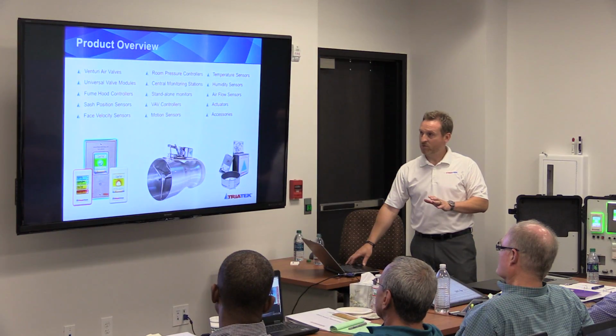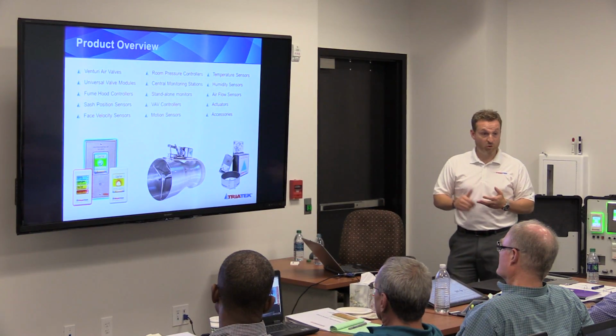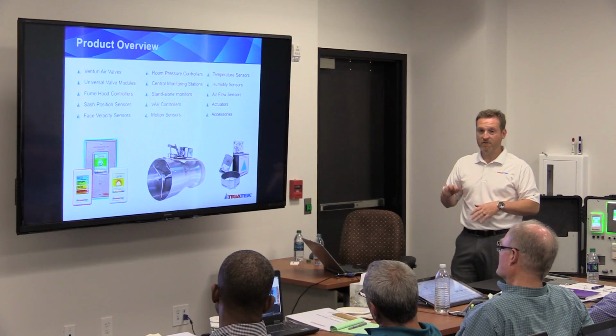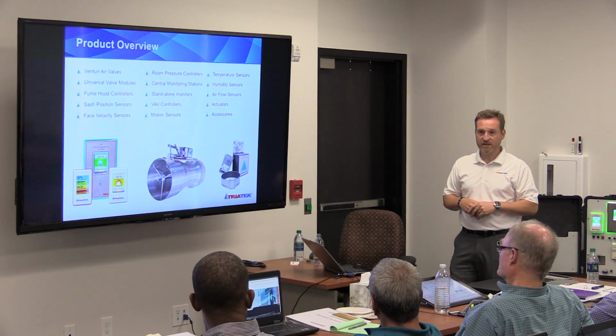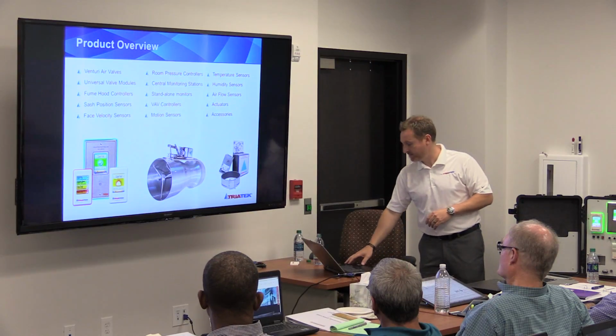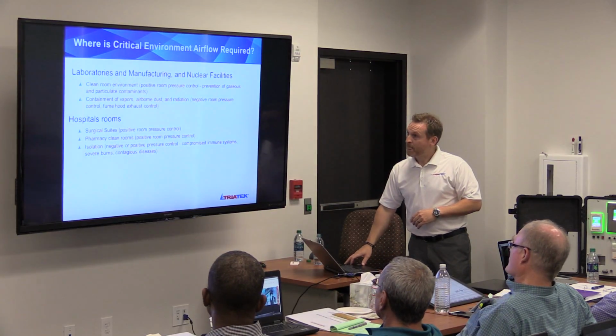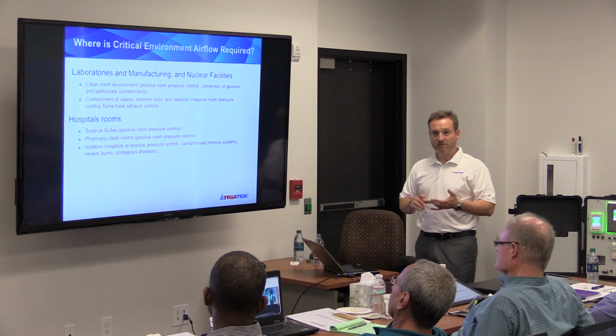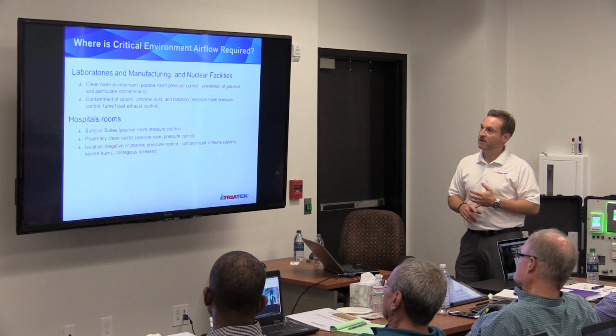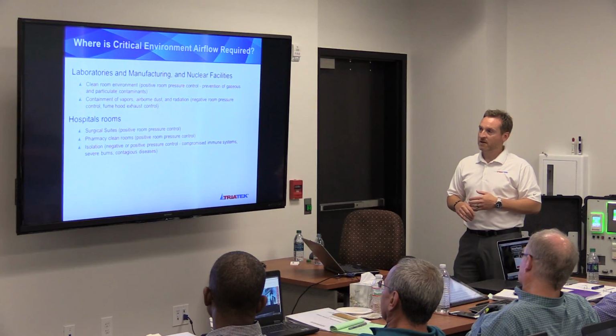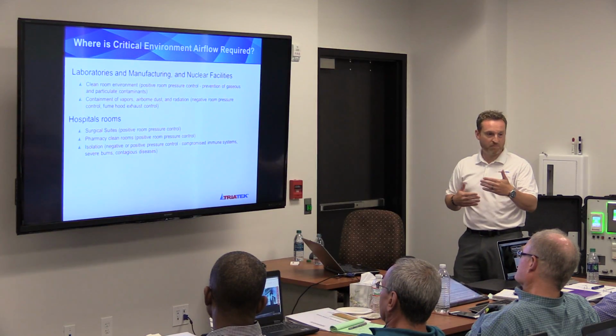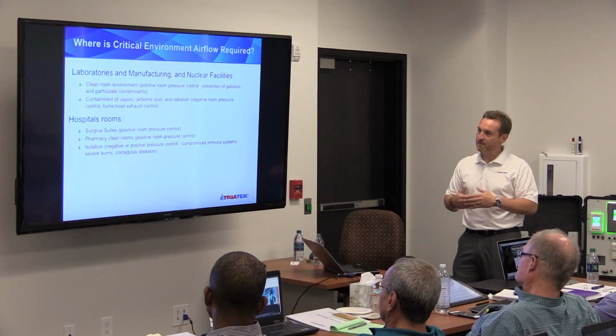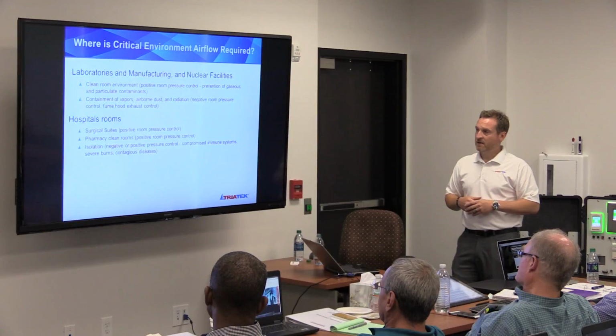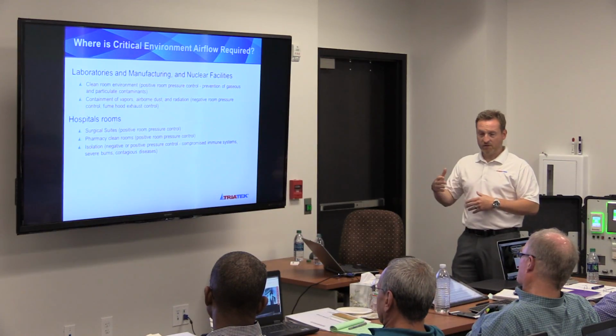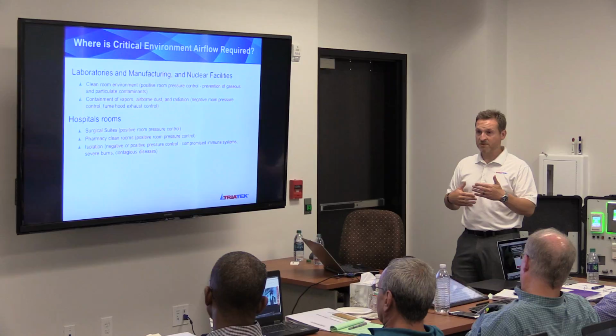And then our product overview quickly: venturi air valves, room controllers, fume hood controllers, and all the ancillary products that will be associated with those applications. Where critical airflow is required, as I said, clean rooms are a primary product area where we provide those controllers. Basically, any space that you want to produce a positive or negative pressure, right? Hospitals, surgical suites, pharmacy in the hospitals. All these facilities require high-speed pressurization control. Okay.